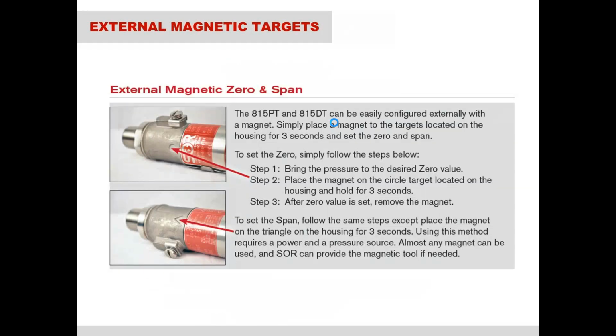same 316 stainless steel housing. Like I was talking about, we have the external magnetic targets. So this is on all the 815 series that you'll see on the casting. You'll see a circle, and then you'll see a triangle on the housing. This circle there, if you place a magnet there for 3 seconds, at whatever pressure is being seen by the pressure port at that time, it will set the 0 to that pressure. And then the same thing for the triangle on the span. So this is useful for a quick calibration of the unit.